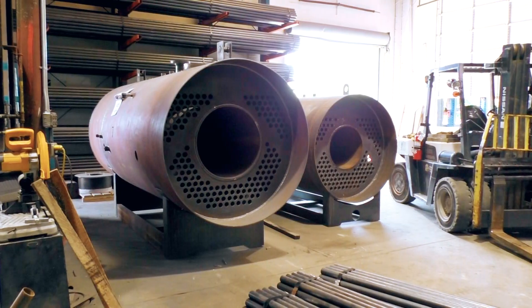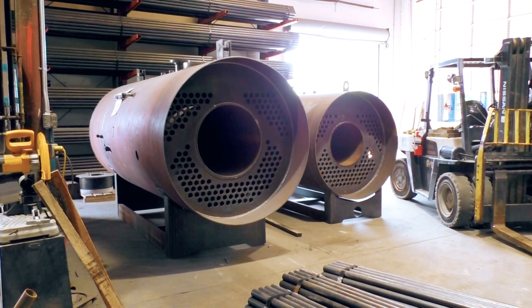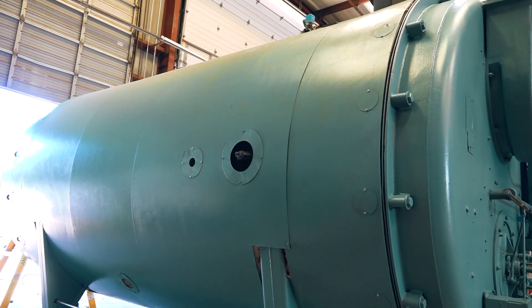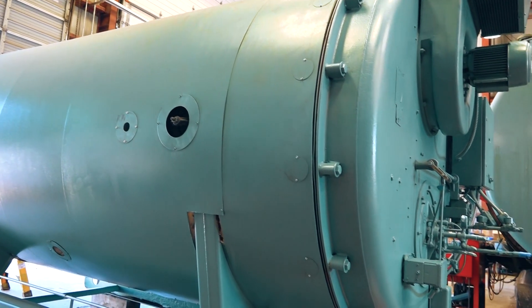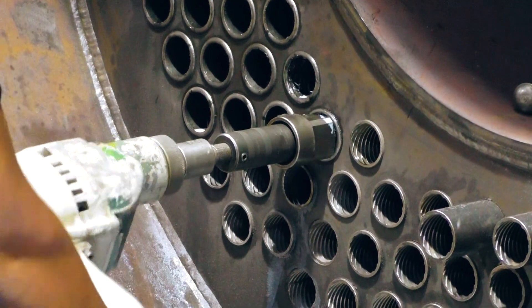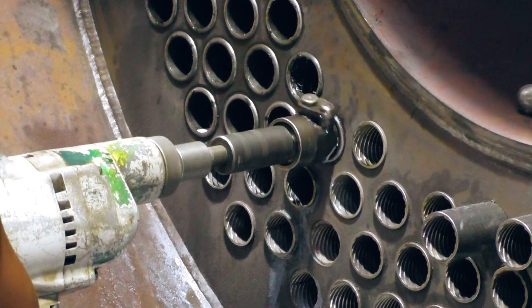Early in the 1900s, a law pertaining to operations of steam boilers was adopted by the state of Ohio. The law states that a facility shall not operate a boiler over 360 square feet without an operator. There are several stipulations surrounding these conditions, but in short, this code requires that any boiler over that size, as per ASME sizing regulations, will require a licensed operator.